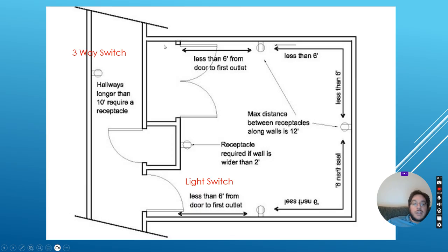Now, having said that, you have to have receptacles everywhere. So anywhere that's a bedroom or a living room or a family room or an office needs to have a receptacle on any wall that is wider than 2 feet, and you need to have a receptacle within 6 feet of the door. And then if we go horizontally along the wall, then the receptacles must be no more than 12 feet apart. So every 12 feet I should have a receptacle, and 6 feet from any door.